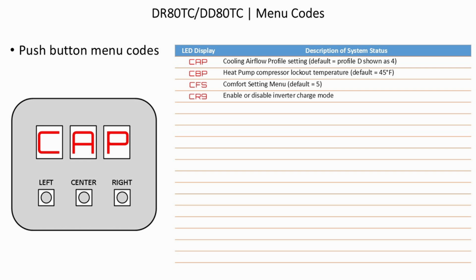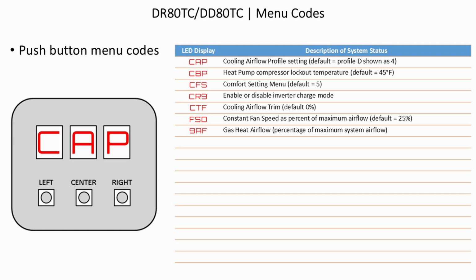CRG, Enable or Disable Inverter Charge Mode. CTF, Cooling Airflow Trim, default, 0%. FSD, Constant Fan Speed as percent of maximum airflow, default, 25%. GAF, Gas Heat Airflow, percentage of maximum system airflow. GFD, Gas Heat Fan Off Delay, default, 90 seconds.